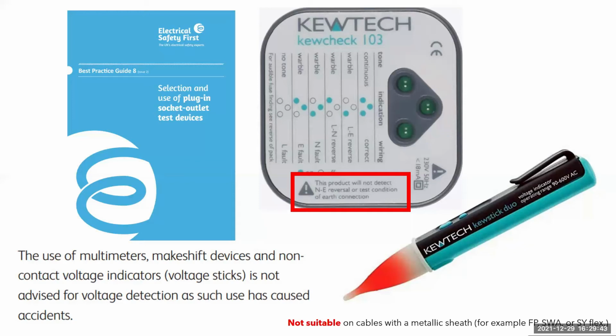So let's put that into context in the real world. If you were, for instance, about to move a metallic washing machine or dishwasher, which is a Class 1 accessory, and you're about to pull it out, the first thing that you would do is put your volt stick against it. If it illuminated, that would mean that the device is not earthed correctly, okay? And that will help you make a judgment as you're pulling the machine out, obviously isolating it first.